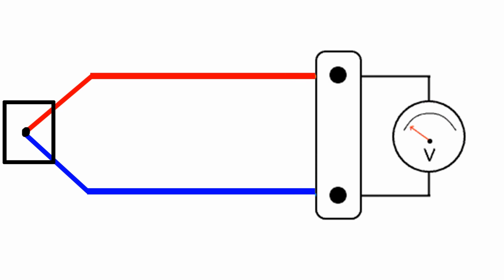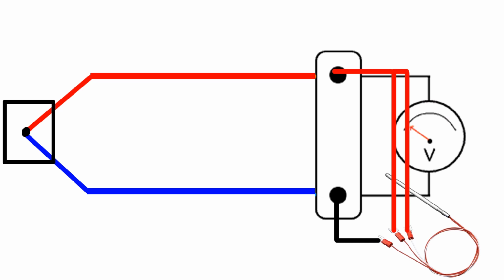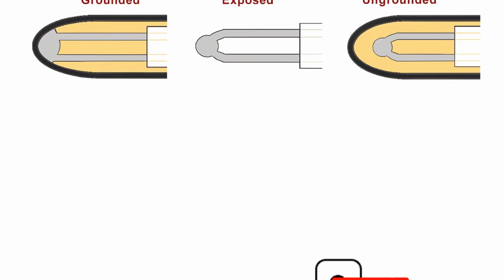In modern systems, however, it's not practical to maintain ice, so we use cold junction compensation. This means the instrument itself measures the ambient temperature at the terminals, usually using a small RTD sensor, and mathematically corrects the reading so the final output reflects the true temperature at the hot junction.